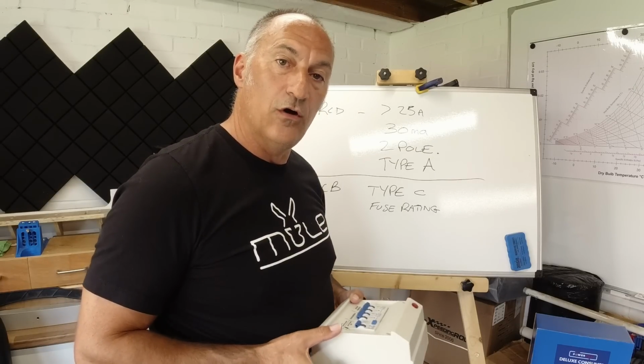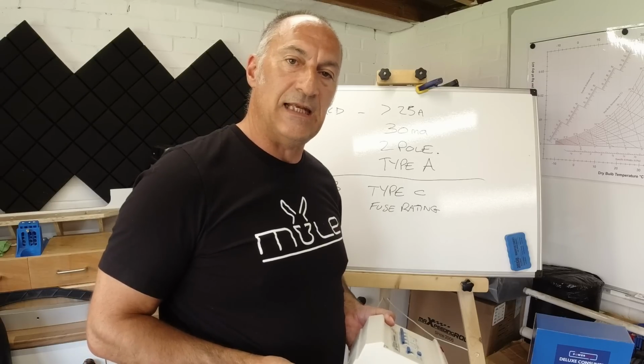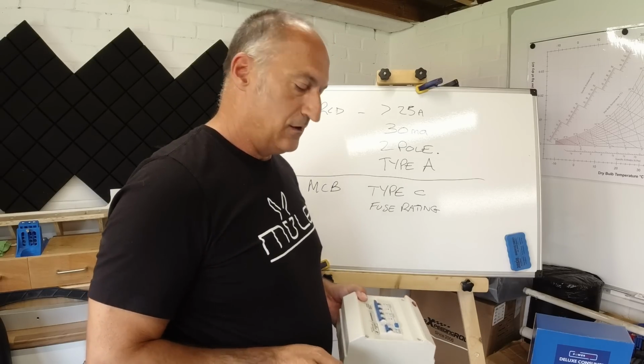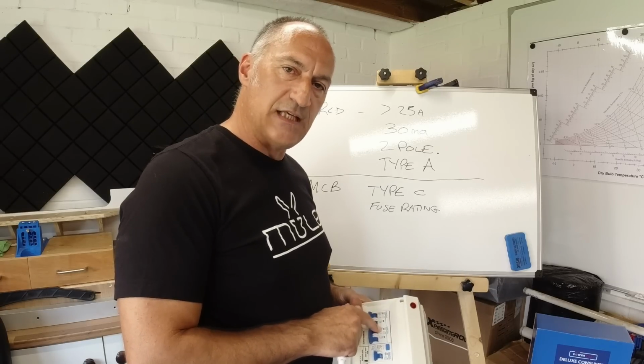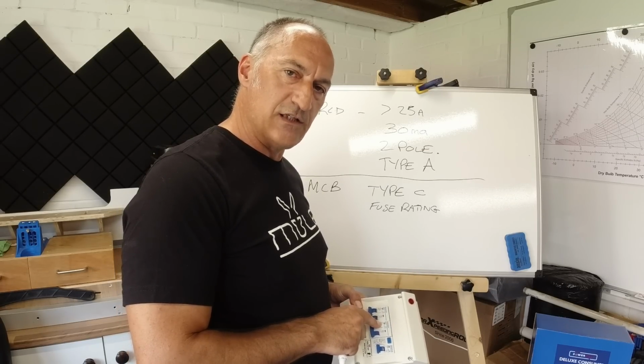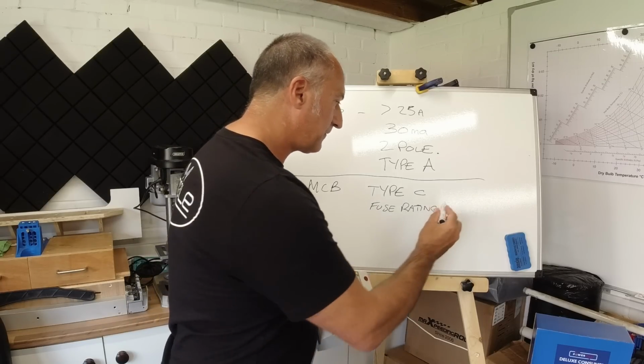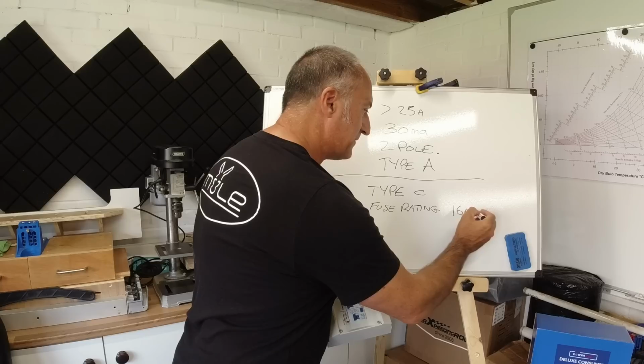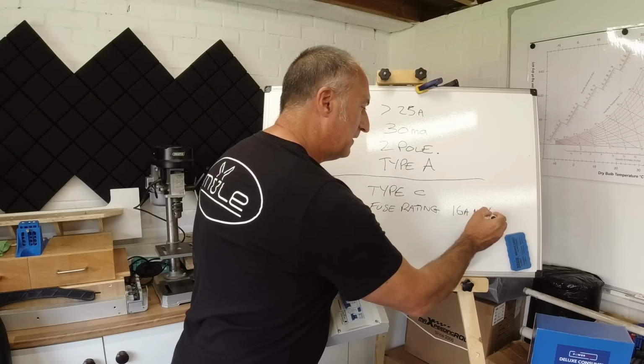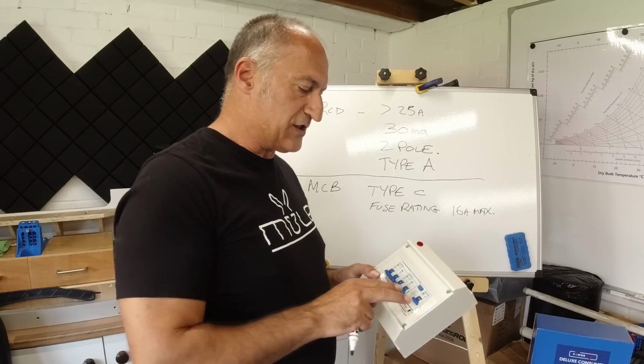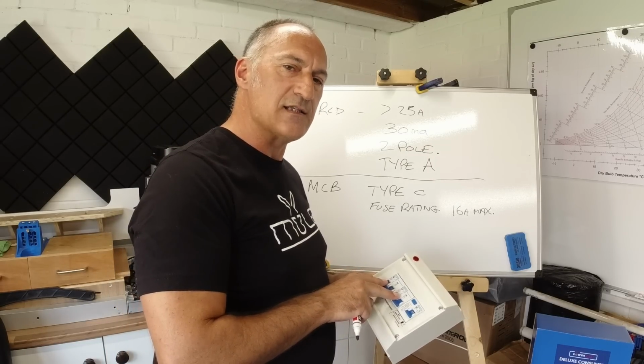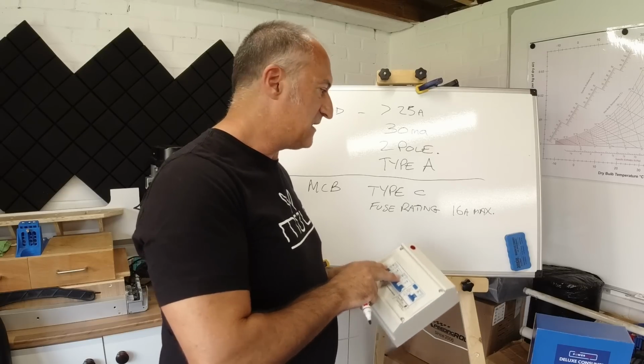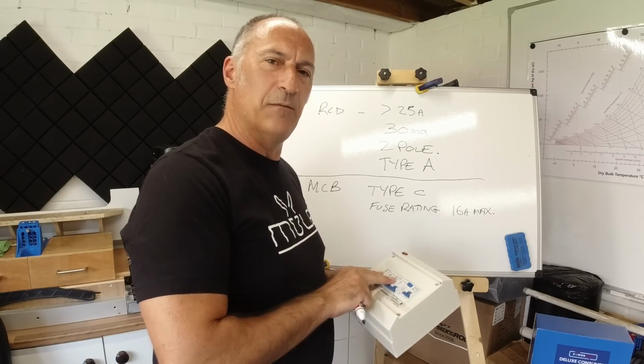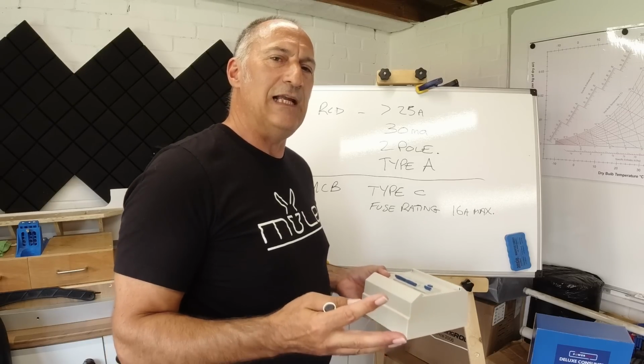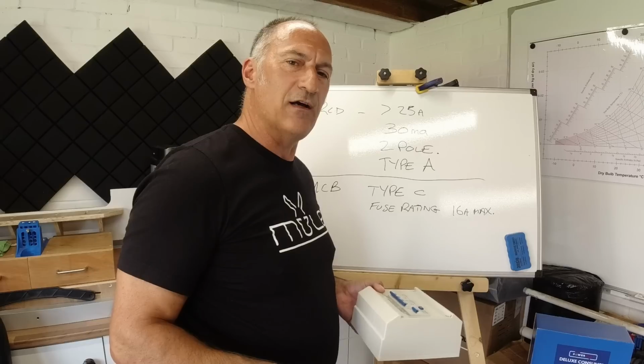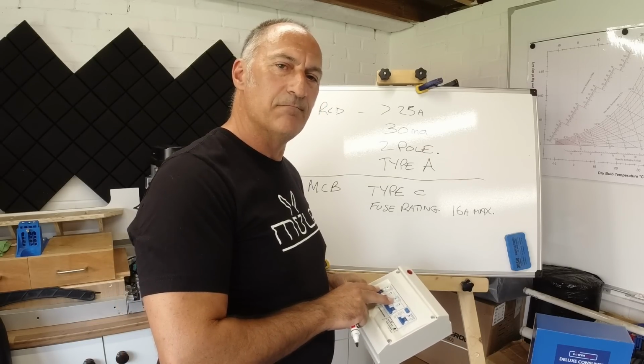Now all campsite hookups are no more than 16 amps single phase. So you wouldn't want any of these MCBs in this device to be more than 16 amps. So I would say that 16 amps wants to be your maximum. And realistically, if you're going to split that load across a couple of circuits, then those individual circuits need to be less than that. They need to be a combined amount. Otherwise, you've got to be really careful not to plug in too many devices and overload the system.